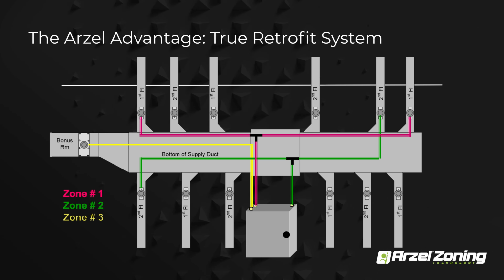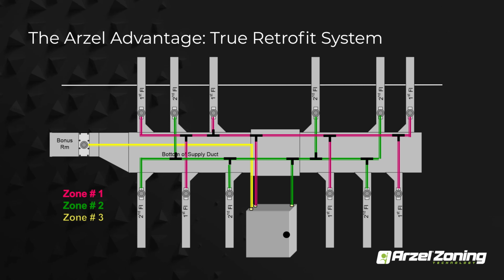This is just a brief diagram here on how you would actually run the tubing for our zoning panels. If you look there, there's a green, pink, and yellow tube leaving the panel in the middle. If you follow the yellow one, it goes directly to a trunk damper. So it's your typical application for a trunk. It'll leave the panel and go directly to that damper. If you have 2 trunk dampers on that run, it would just get teed in with the other trunk damper. So essentially, the easiest way to do it is to take your tubing, go all the way to the furthest damper and connect that tubing. And then from there, you cut in your T, staple your line up, and run that to the damper in line. Just work your way back from there, cutting your T's in and connecting your dampers.